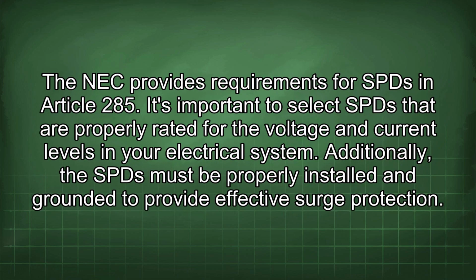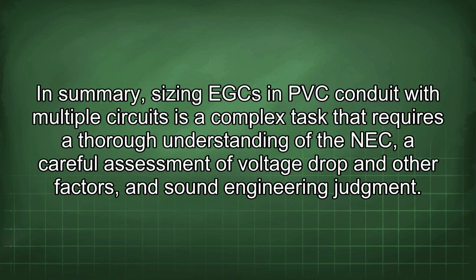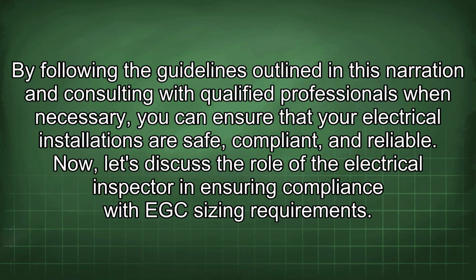The NEC provides requirements for SPDs in Article 285. It's important to select SPDs that are properly rated for the voltage and current levels in your electrical system. Additionally, the SPD must be properly installed and grounded to provide effective surge protection. In summary, sizing EGCs in PVC conduit with multiple circuits is a complex task that requires a thorough understanding of the NEC, a careful assessment of voltage drop and other factors, and sound engineering judgment. By following the guidelines outlined in this narration and consulting with qualified professionals when necessary, you can ensure that your electrical installations are safe, compliant, and reliable.